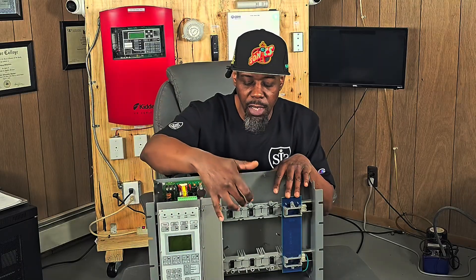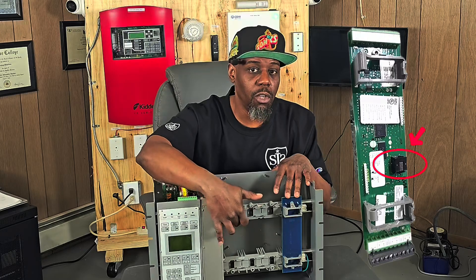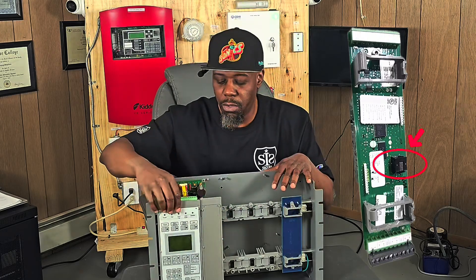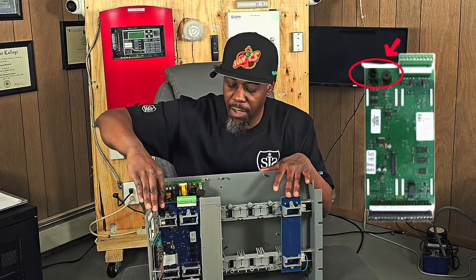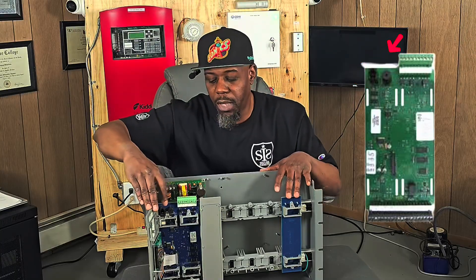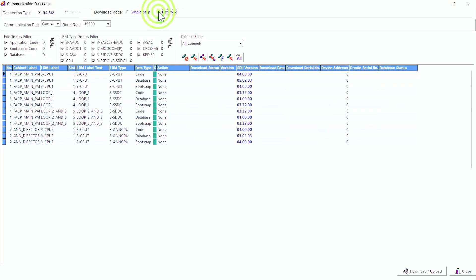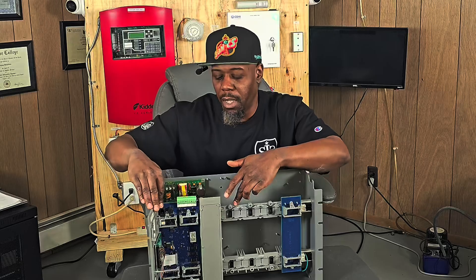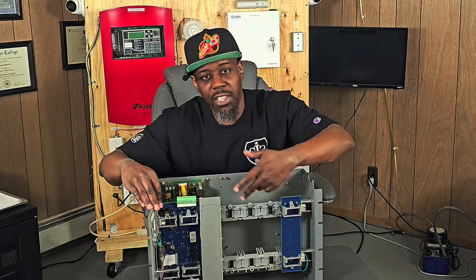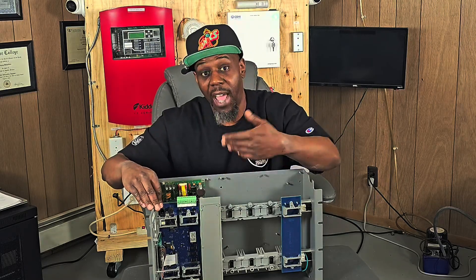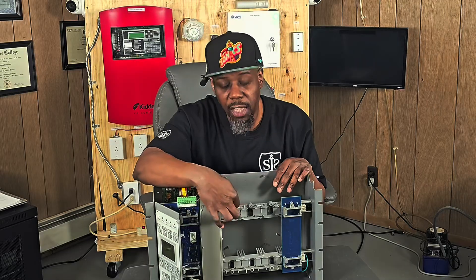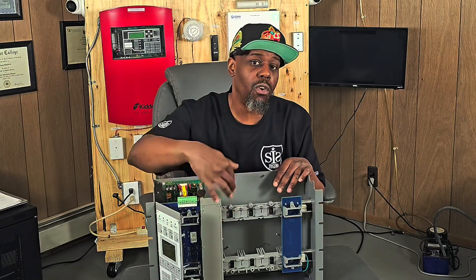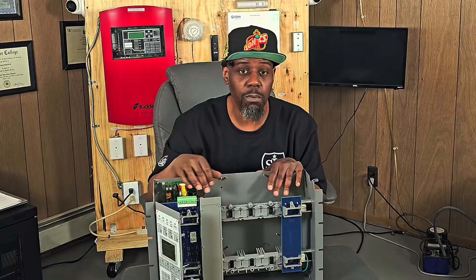So if you have a loop controller here and you're working on a map fault, you could either directly connect to the loop controller, or you can connect to the CPU, which we have here. But if you connect to the CPU, just make sure you select the network option — the radio button network — so that way you can download over the network. From here to the loop controller is essentially like a network connection, so that's why you have to download it as a network. But if you directly connect to the loop card, you will be able to make all your changes locally to that loop card.